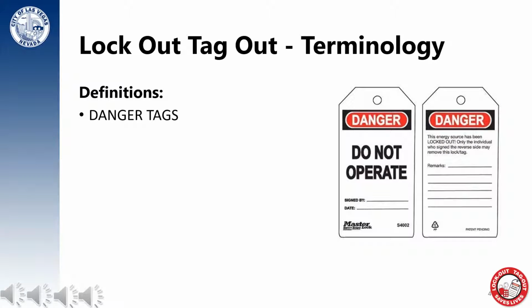A danger tag shall be applied to every lockout in the field along with an operations lock. At a minimum, it should say on it who requested the lockout, what equipment it is locking out, and a work order number if possible. This will help us track this information in the field as well as the energy control log.